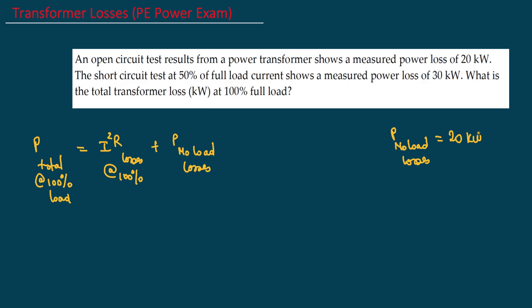The load losses — the I²R losses — come from changes in load current. In the short circuit test, the low-voltage winding is shorted and the voltage applied on the other side is increased gradually until full load current flows through the shorted low-voltage winding. What is given here is the I²R losses at 50% load.